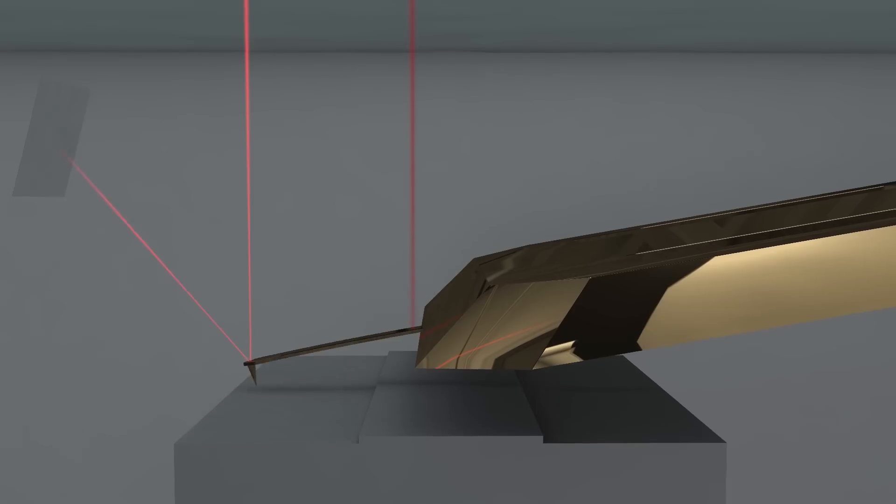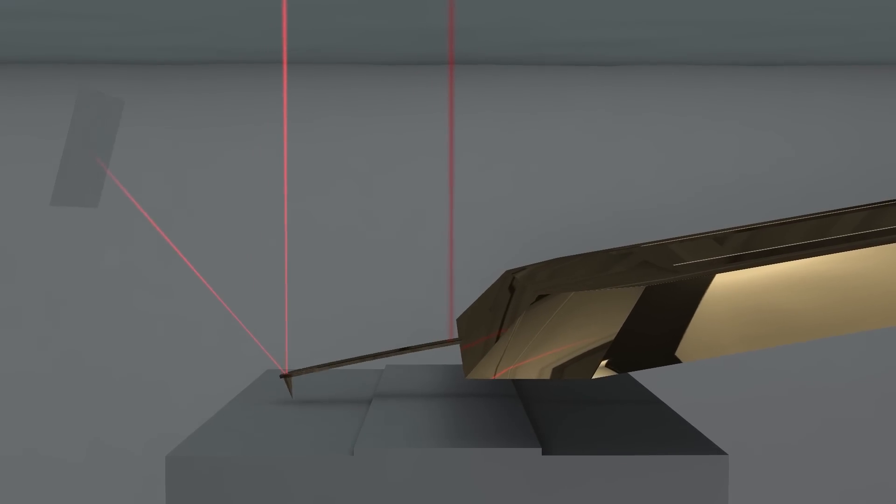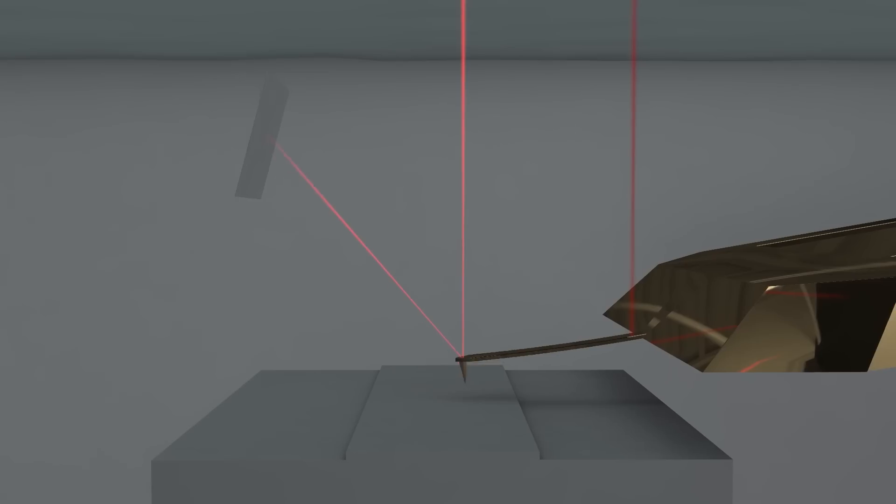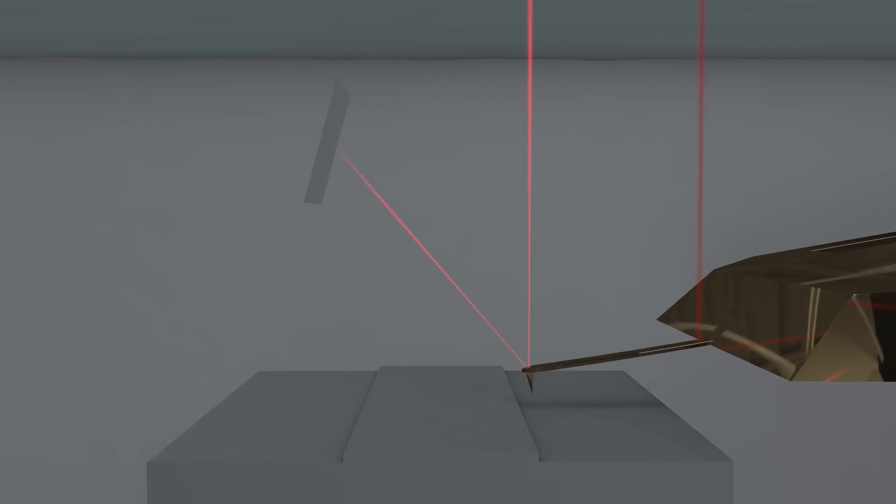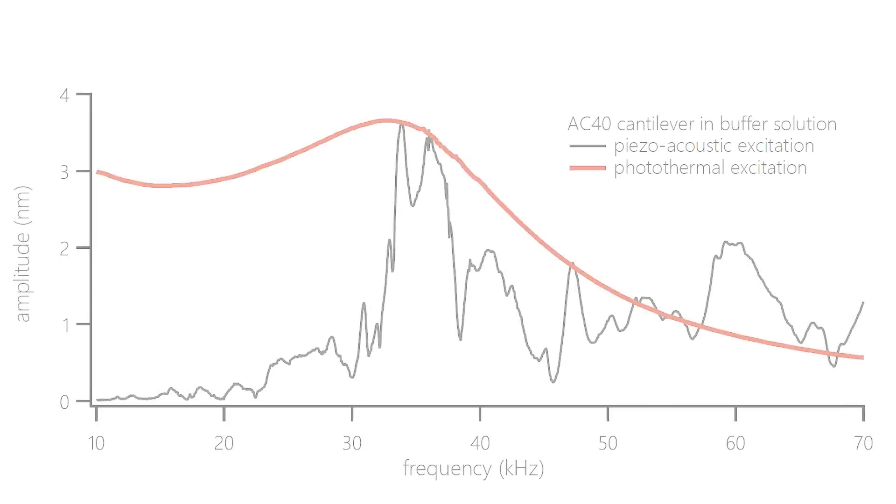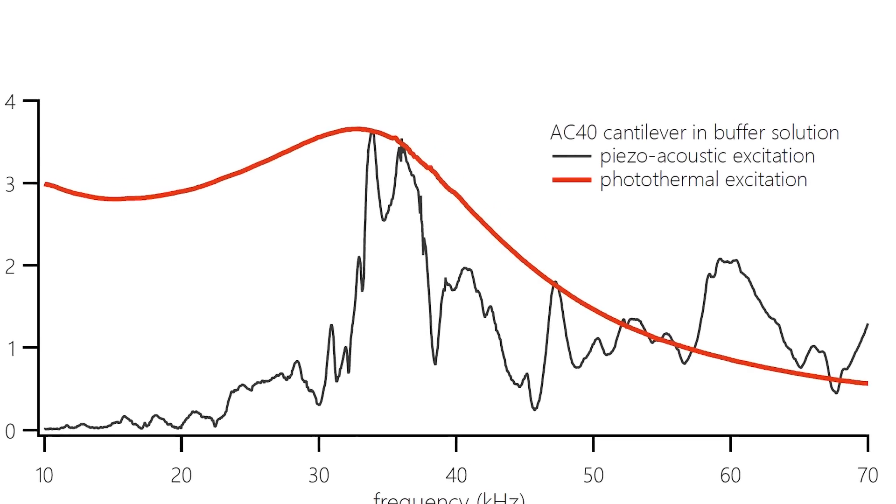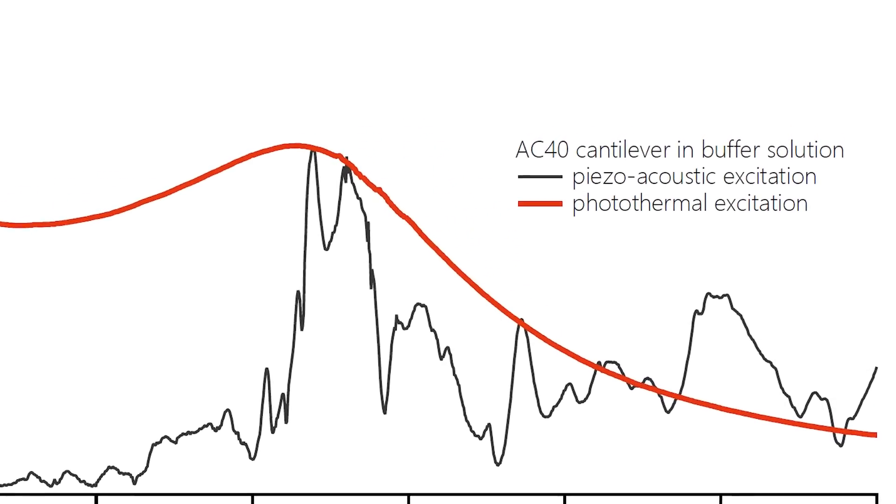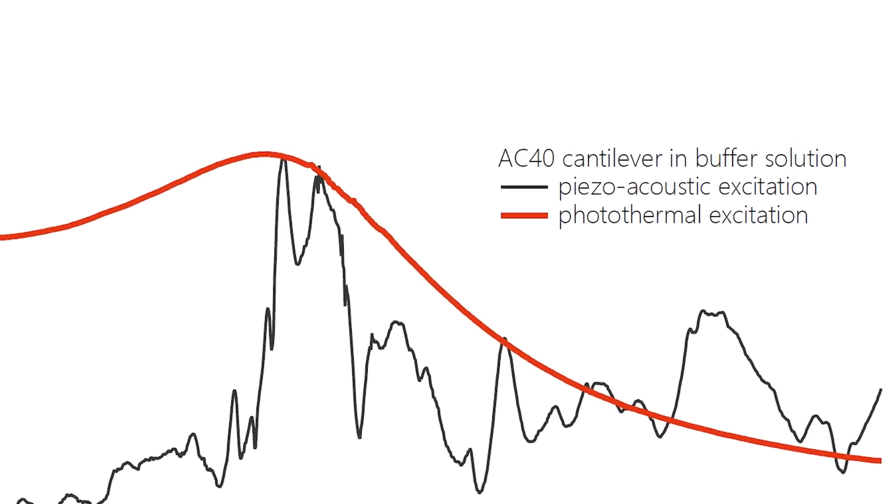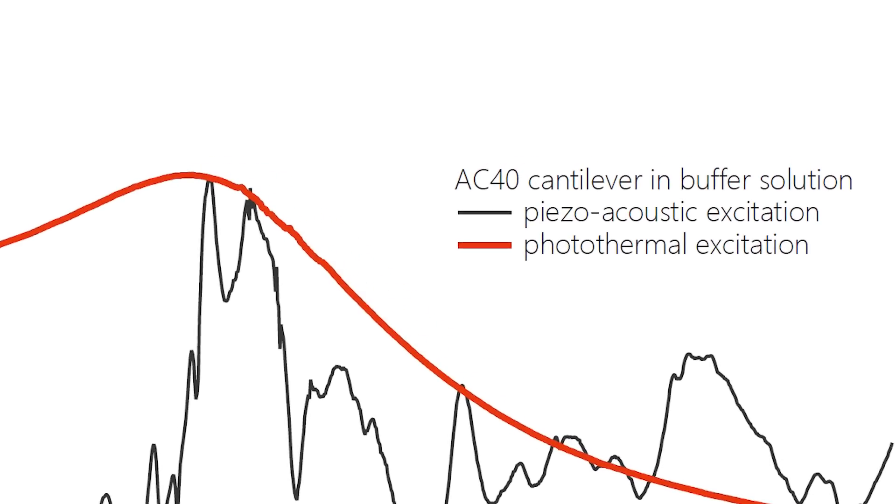Another feature that I like very much is the photo thermal excitation. We call it clean drive. The clean drive allows you to very stably drive the AFM cantilever in any condition. In air, in liquid. It allows you to drive at very high frequencies. It allows you to drive in liquid without the risk of having a wrong frequency that you excite. You get a very nice resonance peak when you do a frequency sweep. In contrast to the conventional piezo excitation, where you just get a forest of peaks and don't really know where to excite your cantilever.